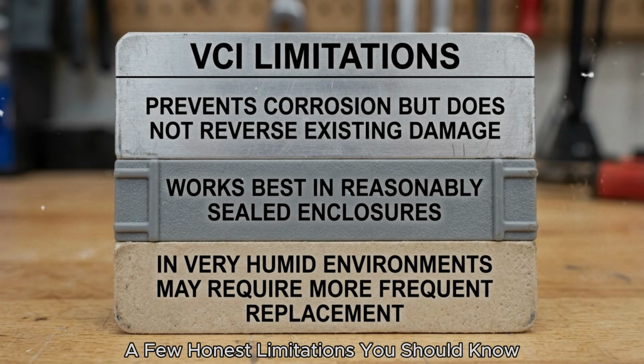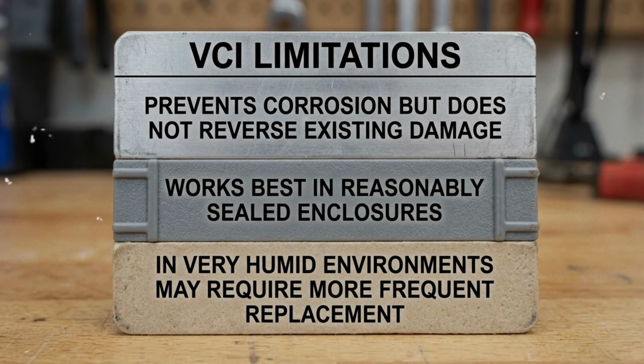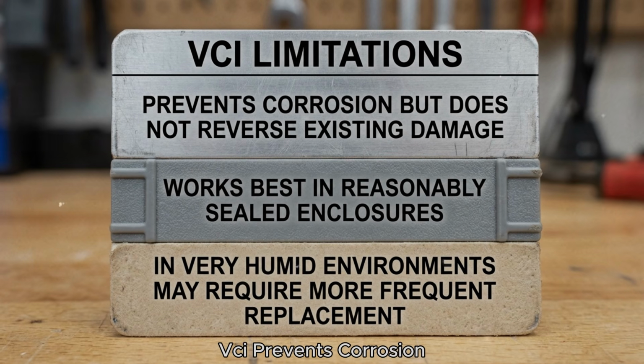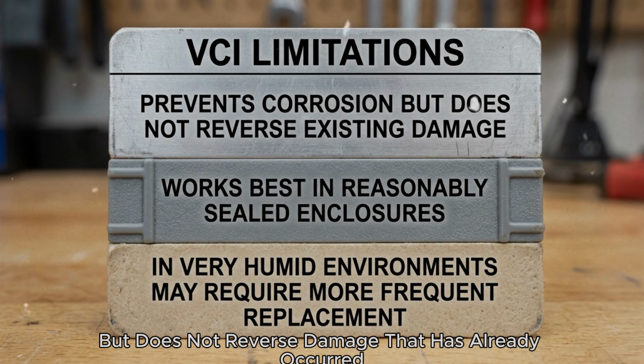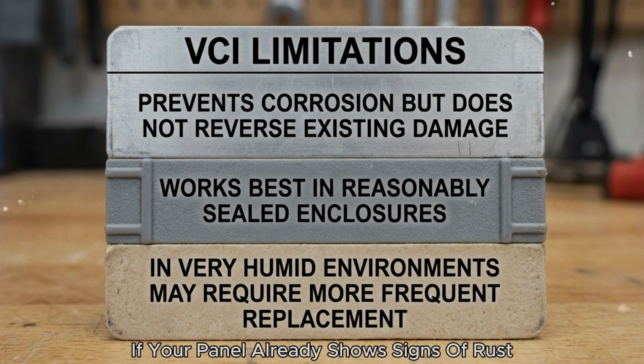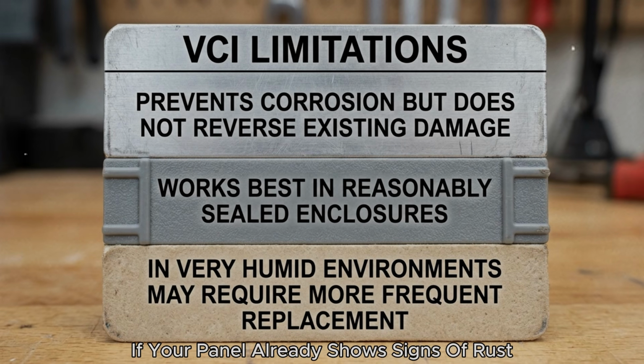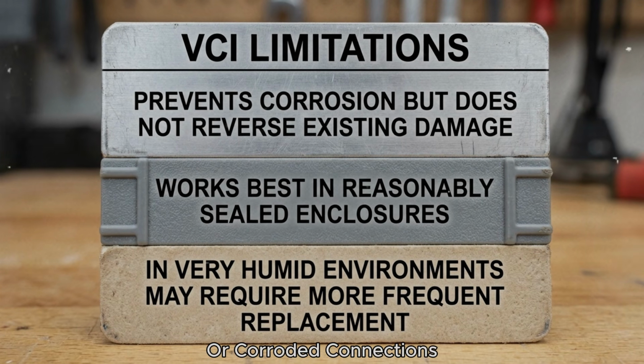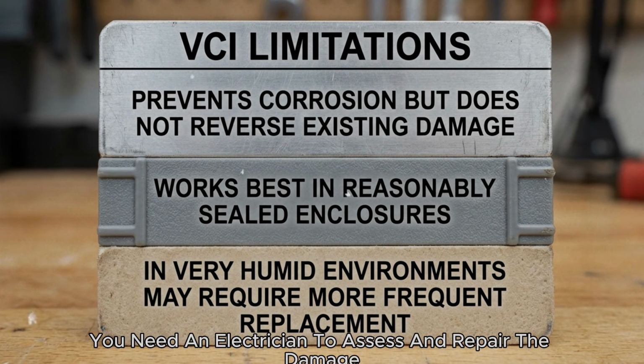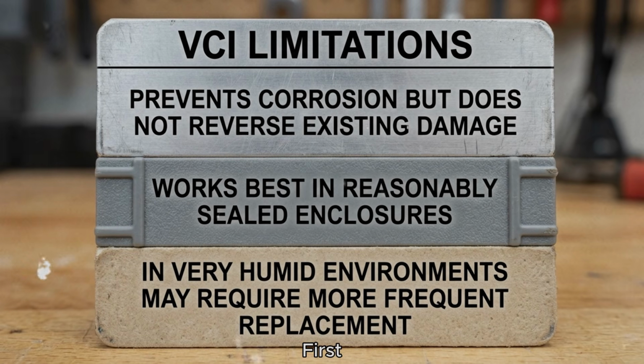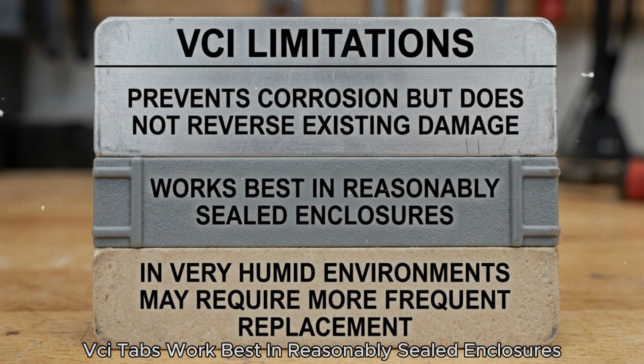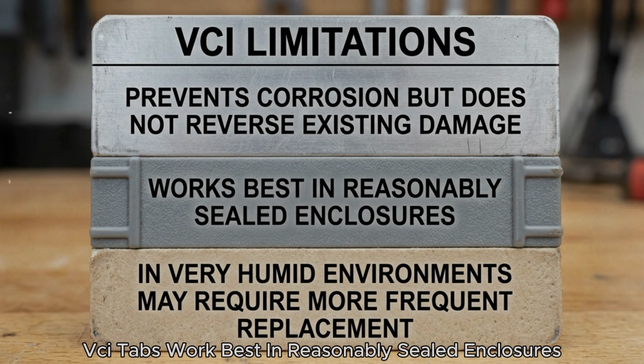A few honest limitations you should know. VCI prevents corrosion but does not reverse damage that has already occurred. If your panel already shows signs of rust or corroded connections, you need an electrician to assess and repair the damage first. VCI tabs work best in reasonably sealed enclosures.